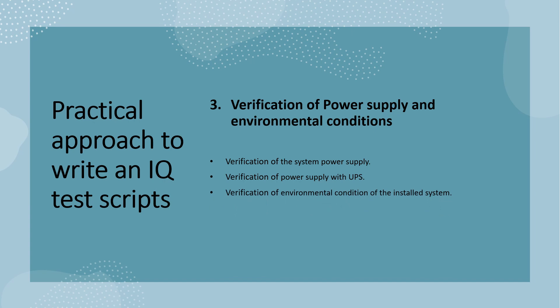The third test script is for the verification of power supply and environmental conditions where the system has been installed. First, verification of system power supply — that the system is connected with a well-established power supply. Next is verification of power supply with UPS, that is uninterrupted power supply, so that if the power goes there should be no impact on the running system. Next is verification of environmental conditions — that the system is installed in a controlled temperature and relative humidity environment.